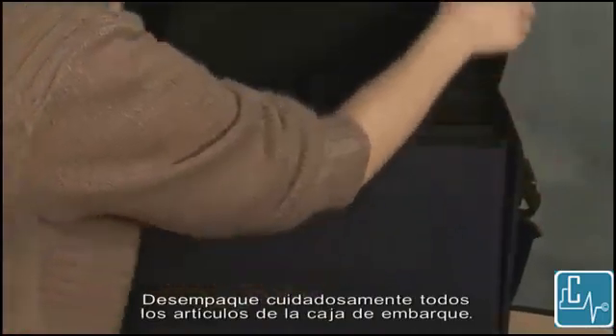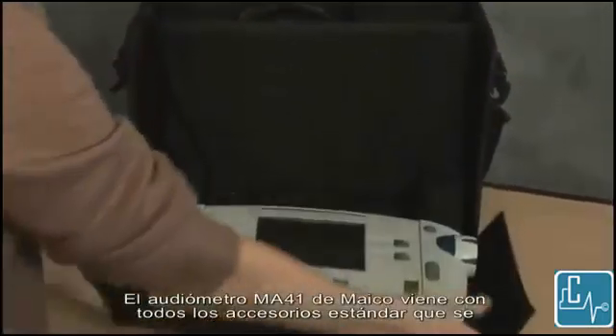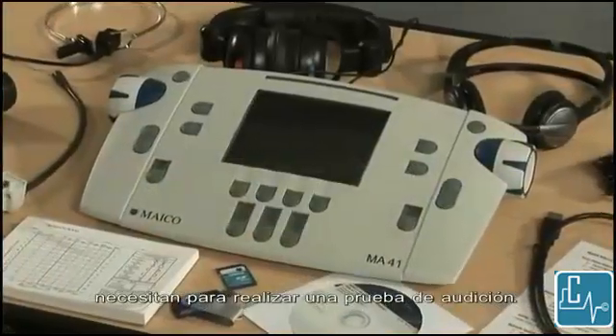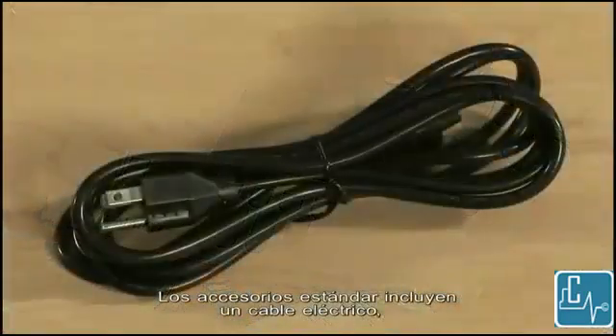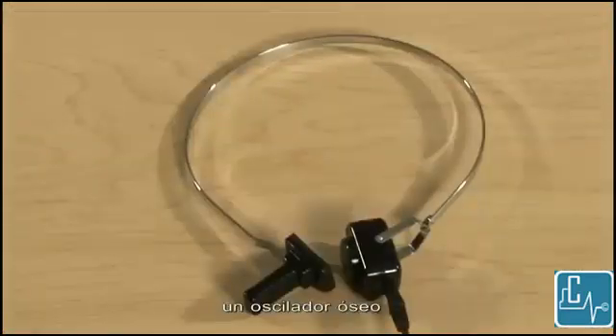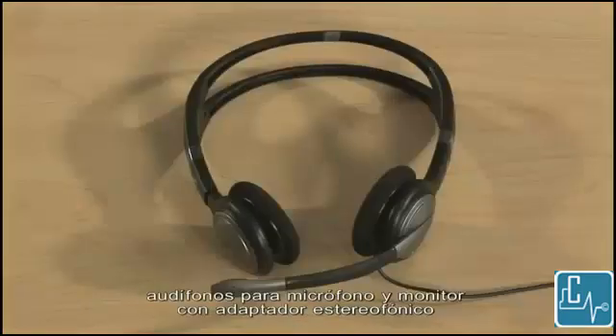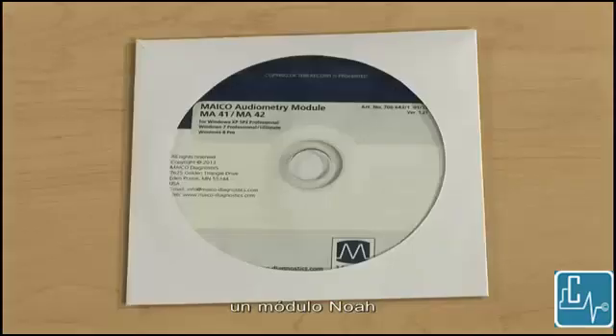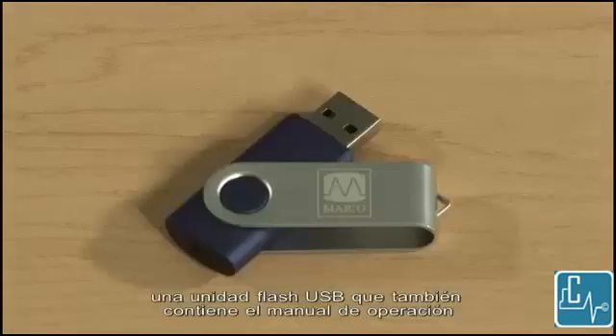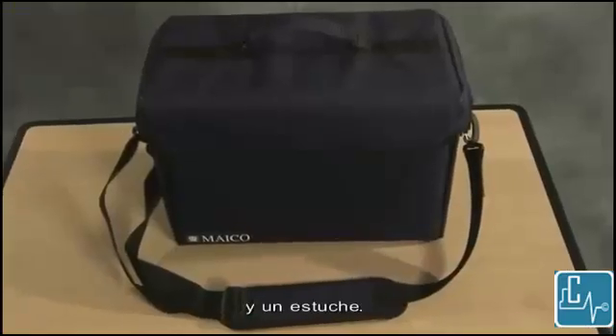Carefully unpack all items from the shipping box. The Maico MA41 audiometer comes with all the standard accessories necessary to conduct a hearing test. Standard accessories include a power cable, headphones, a bone oscillator, a patient response switch, mic monitor headset with stereo adapter plug, SD memory card with WAV files, Noah module, USB flash drive which also contains the operation manual, USB cable, a quick guide, and a carrying case.